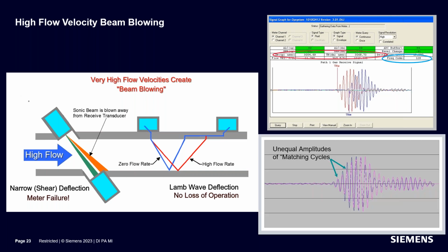So here is a beam blowing condition. If you look at this, this is what we call a correlated plot. So there's a slight difference here. If you notice up here, there's a button that says correlated and it's not checked. So you can see the differential between the two. In this shot, that button would have been checked. And what that does is it says to the device, put those two signals where they would have started from, which is they should be right on top of each other, the equivalent of a zero flow condition.